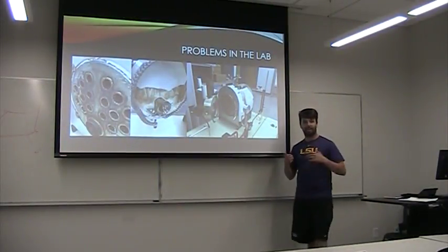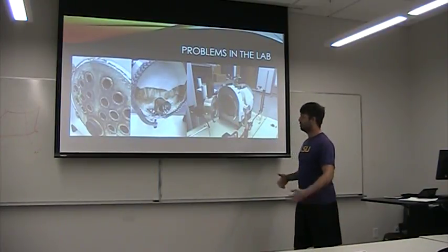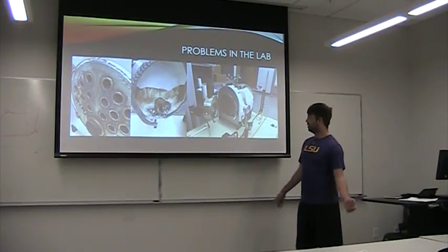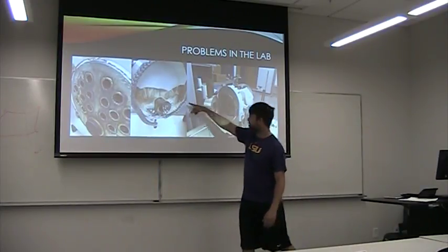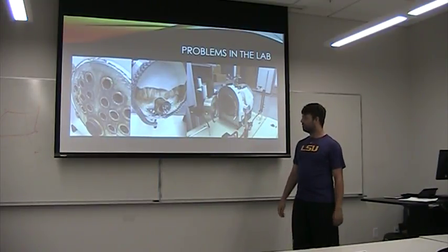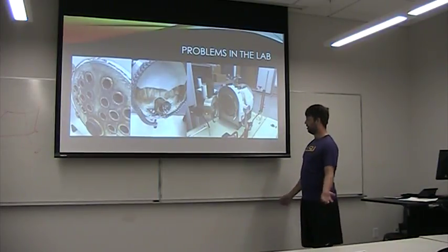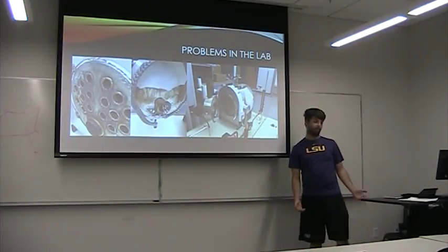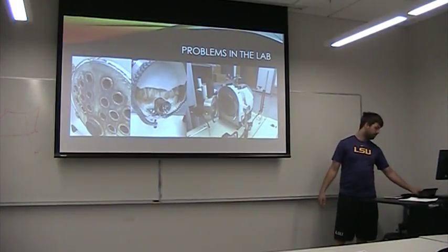To start off, we didn't actually do it last week, so I didn't really get the knowledge that I was hoping to get from doing the experiment because we had a boiler failure. Basically what happened was, you can see all the rust. It's hard to see in the picture because of the lights, but it's real dark and rusty. See here, one of those tubes had a fracture in it because they didn't heat treat the welds right and it caused a flood and a leak. Therefore, it wouldn't hold the water or the pressure, and we could not do the experiment, which was kind of unfortunate because I think it would have helped a lot doing the calculations.